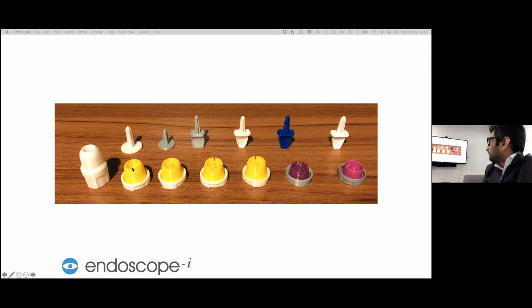The inner now has the valve incorporated here, but you can see we've pretty much halved the height of the snap valve. Now this one had almost like a wedge shape inside. So it was pointed at the tip, and it just had one slit. And even though it was much easier to negotiate once the scope was in, it was actually quite difficult to pass the tip of the scope through the wedge. And certainly on withdrawing the scope back, it was actually getting caught.